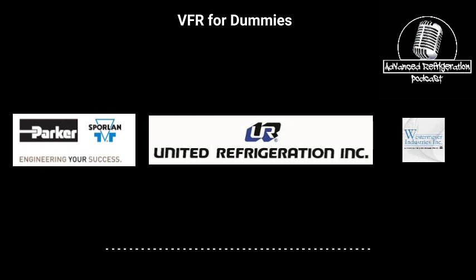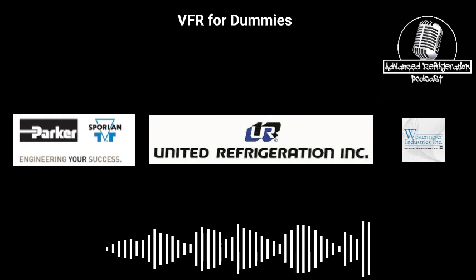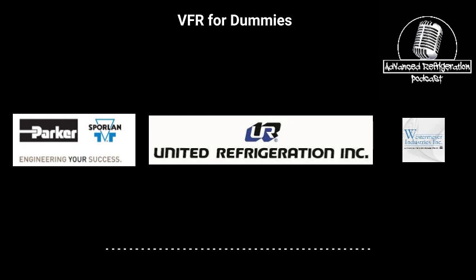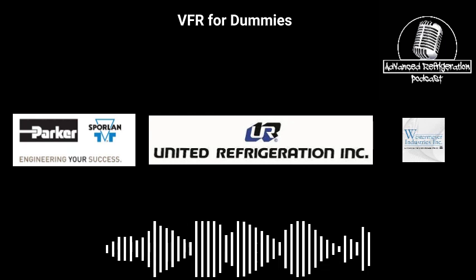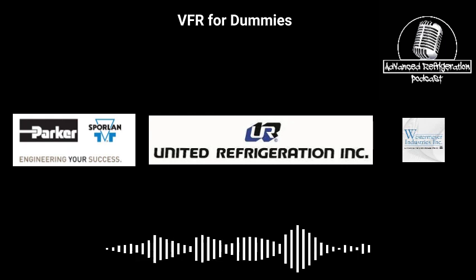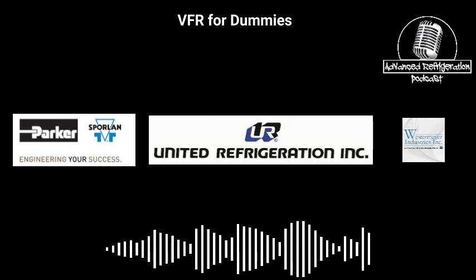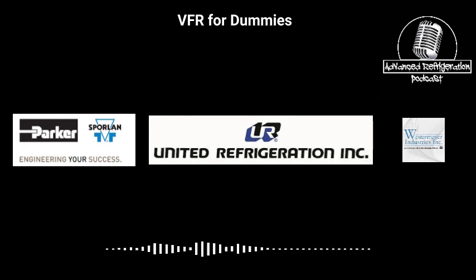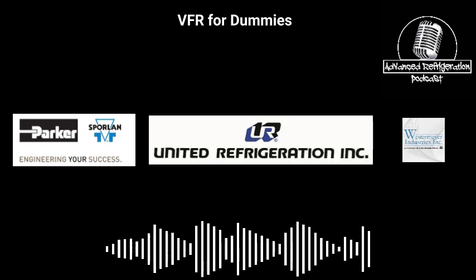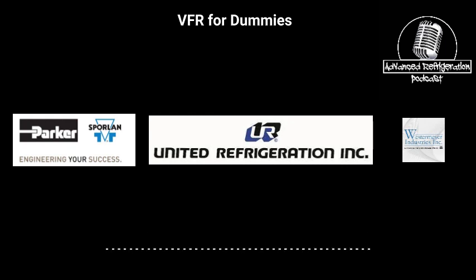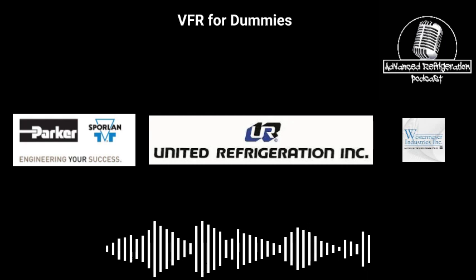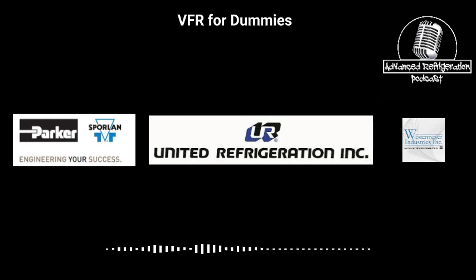Here we go. So the only place we have solenoids is on the outdoor units. Okay. And those are just changing 4 ways over. So this is a 12-port box. 10-port. Yeah, 12. So this is the largest branch selector box, 12 individual ports. So there's our connections coming in and how they filter out to each line set. Can you zoom in a little bit? Yeah. All right. So electronic expansion valve, HP LP valve, and then the secondary expansion valve that's going in the suction, that's going into the high pressure low liquid.